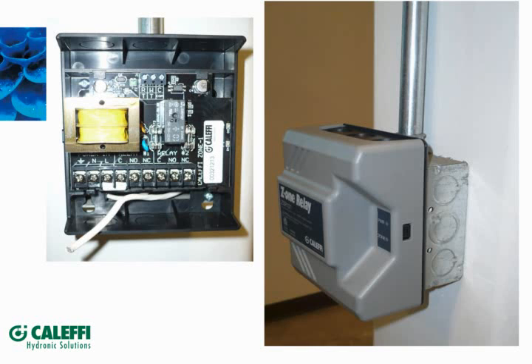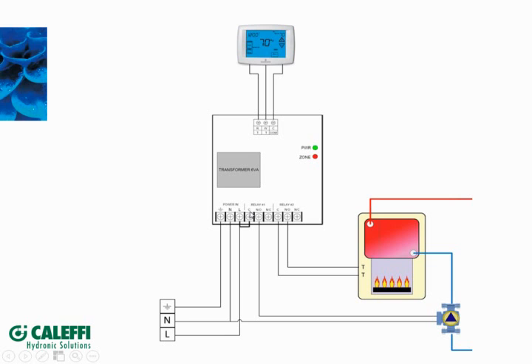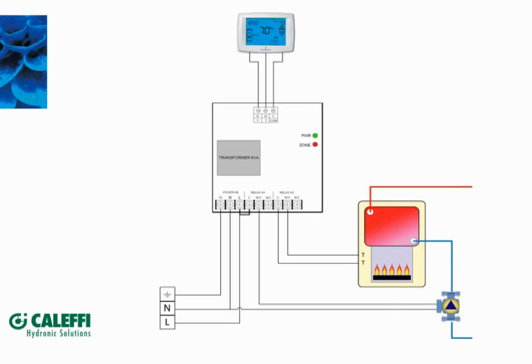So, a typical application. We've got a couple of application drawings here, just showing a single zone, 3-wire stat wired up to here: ground, neutral, and line coming into the control. We've got our jumper going over to common. So if there's a call for heat, the relays fire, and that's going to take your line voltage over to the normally open contact. That's over to your system pump. That'll fire up your pump. And at the same time, the common and normally open are wired up to the TT of the boiler, and that'll give the boiler the heat demand. So, call for heat, pump turns on, boiler fires. Pretty simple stuff. Yeah, probably one of the most common ones too.